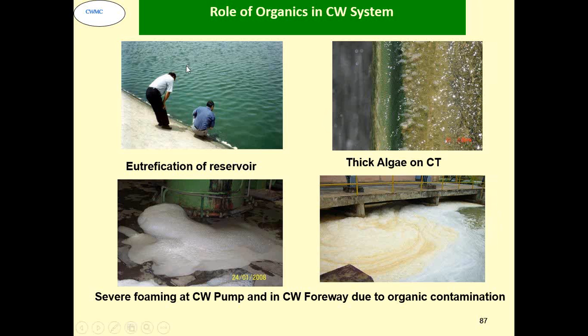Now on the left side picture, this is the make-up water reservoir of a cooling water system. The water coming here had a high level of impurities, especially microbiological or organic loading. Because of this, a powdery green algae formed on top of the reservoir and below. This algae was aerobic in nature, so it took away all the dissolved oxygen from the top of the water, and below that anaerobic bacteria like SRB started growing and fouling the system and causing microbiologically induced corrosion.